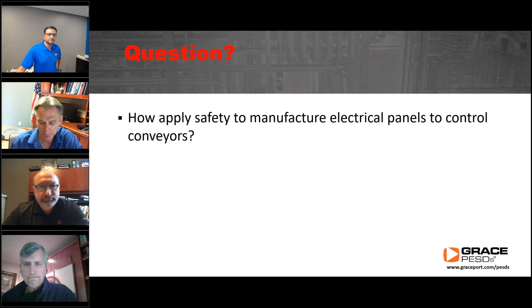Let's go to the next one. This is for Terry: can finger-safe components be considered safe when performing a risk analysis for working near energized circuit parts? So again, when we look at 70E and Z462, they're work-task-based standards, so we have to start with what the work task is. Am I going into some electrical equipment? Am I opening the hinged door? Am I removing a bolted-on cover? There are other issues we've discussed with respect to the energized electrical work permit, but let's set those aside and specifically look at shock risk assessment.